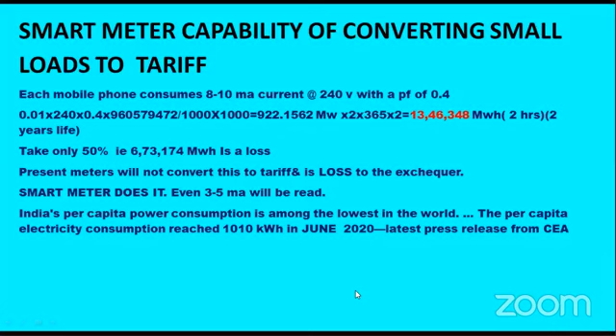So with this advantage, why smart meter? Smart or advanced meters are different from standard kilowatt hour meters in two main ways. First, the meter can measure and record both cumulative usage and highest demand for time intervals as small as 15 minutes, even less. Secondly, the meter can remotely communicate with a utility meter reading system, either wirelessly, by telephone, power line, Ethernet, or any other mechanism with which communication is embedded into the system technology. Although interval meters have been in place for many years, it is the total combination of holistic time-of-use measurement and communication in a smart meter that gives utilities advanced program and billing options for more customer services.